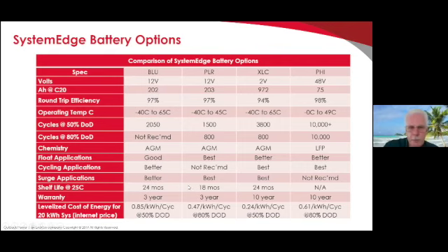Shelf life is pretty good across the AGMs. Same with the SimpliPhi, they don't specify it, but they do have long shelf life. Self-discharge rate is pretty low. Warranty is 3 years on the Blue and the PLR, 10 years on the XLC and the SimpliPhi. And I think for the SimpliPhi, that's if you only use 80% capacity of the battery, so if you charge up to a lower voltage.